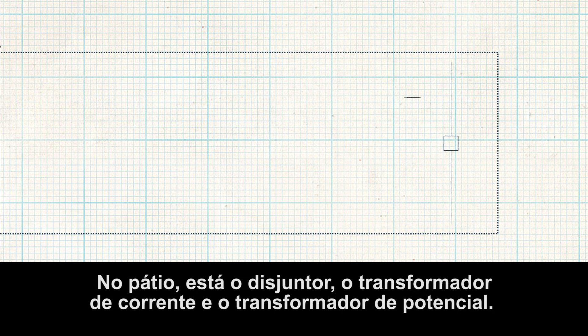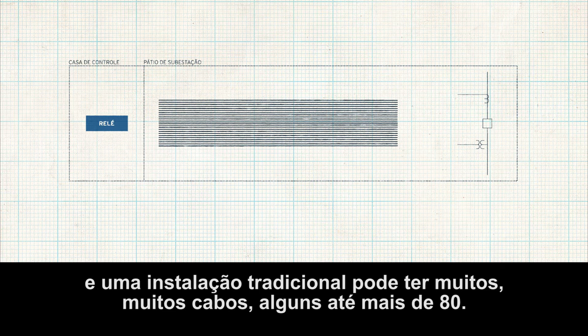Today I want to talk to you about our new TiDL technology, or time domain link technology. If you take a look at a typical installation, you've got the relay in the control house, and then out in the yard, you've got your circuit breaker, current transformer and voltage transformer. You need to get all those signals into the relay, and so we run all those copper conductors. A typical installation can have many, many conductors, some as many as 80.